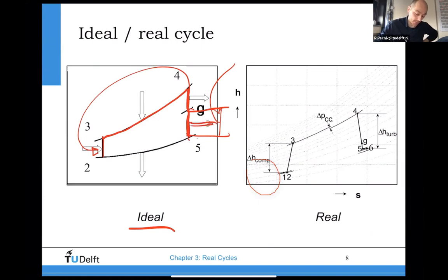And this is then closed again, not really closed, but it is thought of as a closed cycle, although actually the exhaust is going to the environment. But then, of course, you don't have this ideal case. You have a bunch of things that happen. A gas turbine actually has an inlet, and in the inlet, you can even filter or heat up the air or cool down the air before it goes into the compressor. And at the inlet, you have pressure losses.